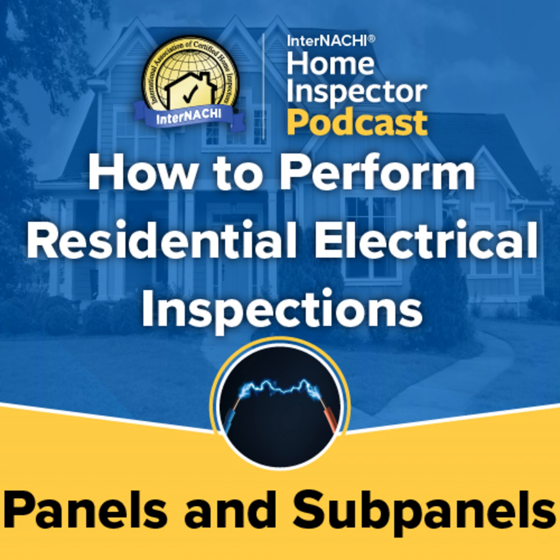Distribution panel board or subpanel. Distribution panels or load side panels are downstream from the main panel containing the main service disconnect. In these panels, the neutral and grounds should be separate and the neutral bus should be isolated from the panel enclosure. The only exception to this is in existing detached structures where no metallic path exists between the structures. In this exception, a connection between the grounded conductor and the metal case via bonding jumper is permitted.